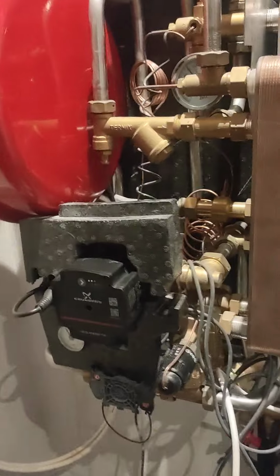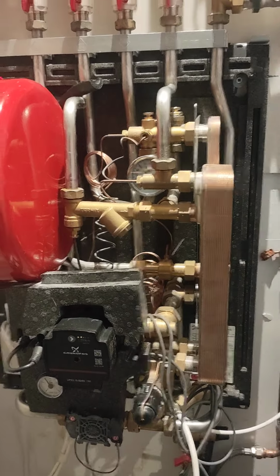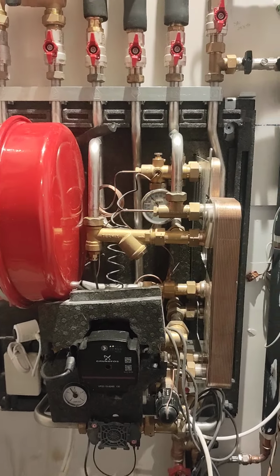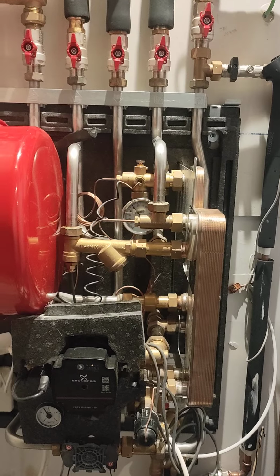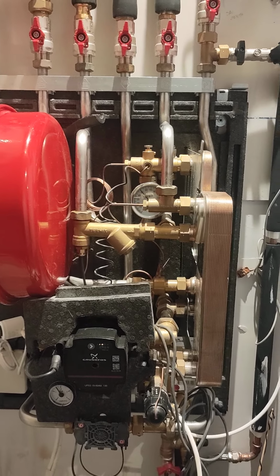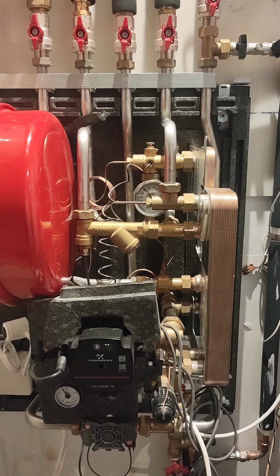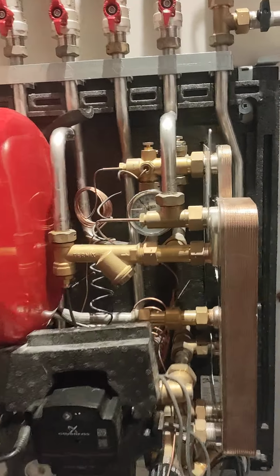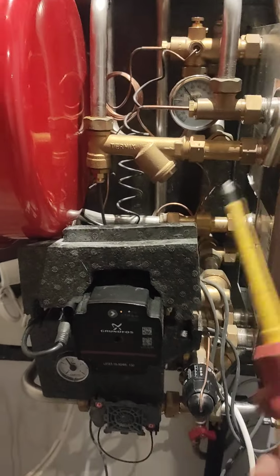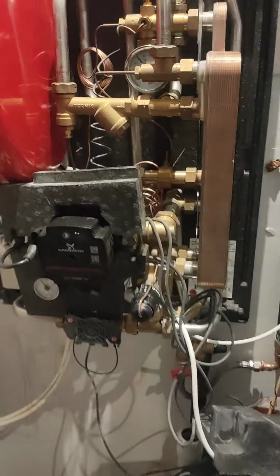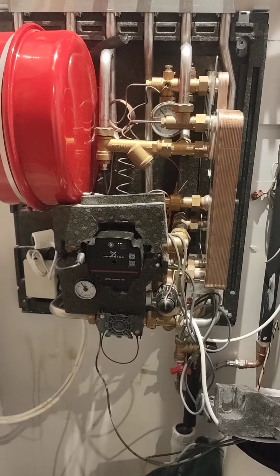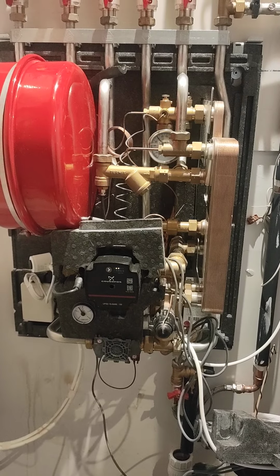Every time I come to this unit and people complain that there's only 2 or 3 radiators working and the rest are cold, I find 2 problems: either this plate heat exchanger is blocked, or the pump. In fact, mostly the pump is not fit for purpose.